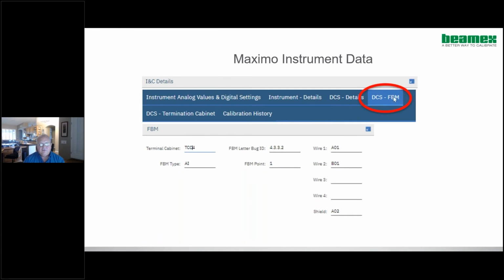Here's more of the hardware address — it gives you your cabinet, your hardware address ID, and your point number. This happens to be point 1. This one gives you your wire numbers — there are 3 wires, and these wire numbers will be located on the wire itself. So when the guy's out in the field, he scans that QR code and can get this on his phone.